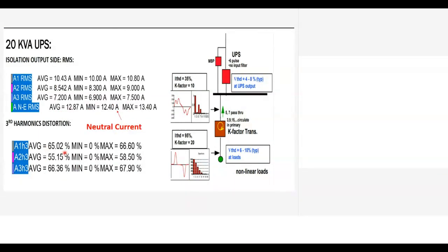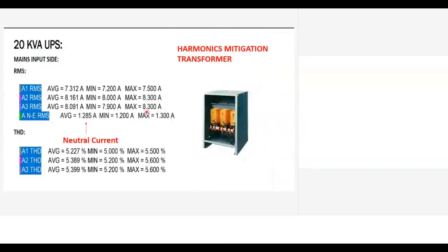And the maximum harmonic current was very high. Third harmonic was very high. But after we installed this isolation transformer, we found that the load was balanced, current was reduced, and if you see the neutral current, it's coming down to 5%. So excellent performance by this type of transformer.